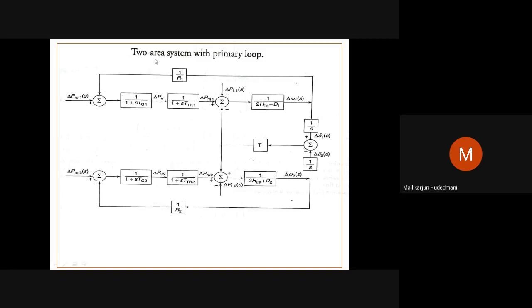What does it exactly represent? Are we able to recall something we learned in module 3A? Yes, this represents an isolated area initially. I am speaking only about the upper half, with the governor represented by a first order lag function and the turbine represented by a first order lag function. Then I go with the area and the response of the frequency sensitive load and frequency insensitive load representation, and the deviation of the frequency that occurs in that area is fed back through the droop of that governor to the input correction of the governor, wherein I have the P reference set point from the speed changer reference set point and the actual power fed with the deviation and the droop, which is compensated with the summer block and fed as a request for the governor to change the position.